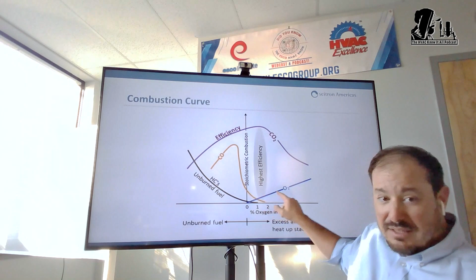If I put my probe in the stack, guys will call me and say, well, I have 0 CO, so it must be running clean. And when I ask, okay, what's your oxygen, because that's the king in combustion, they say, well, it's 10%. Guess what? If you look at the curve, your CO is 0, but your oxygen is way too high, almost double the amount, if I'm at 10% when I should be between 5 and 7. So look what happens to my CO2 and my efficiency.